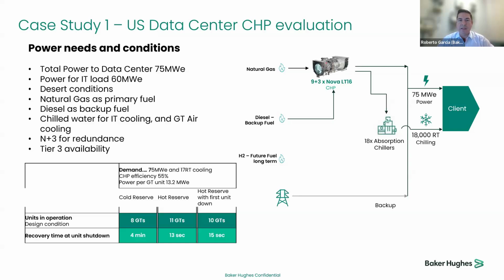This high availability is reached using the N+3 configuration: 9 gas turbines working with 3 spare engines. Many different operational scenarios have been discussed and evaluated. Some include cold reserve, meaning spare units are down but ready to operate if a running unit shuts down. Other scenarios include running additional turbines beyond the 9, like 10 or 11 units, with some spinning reserve available.